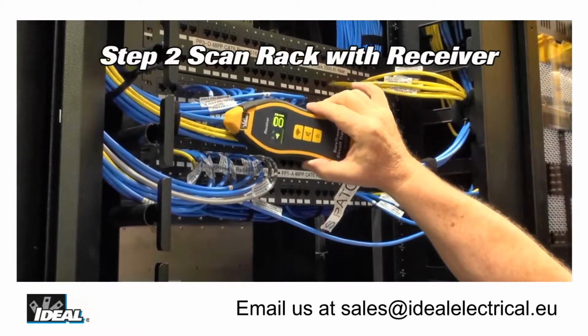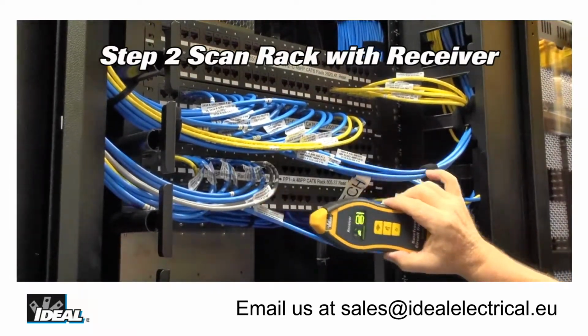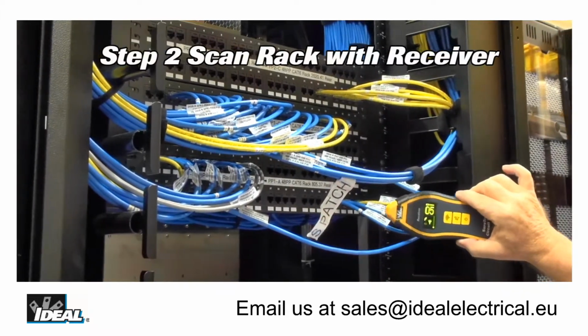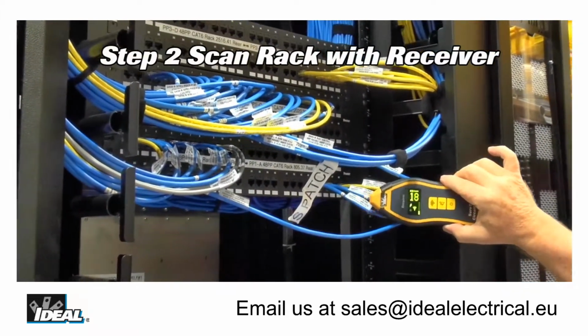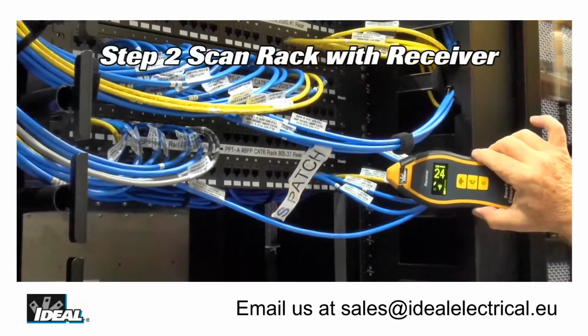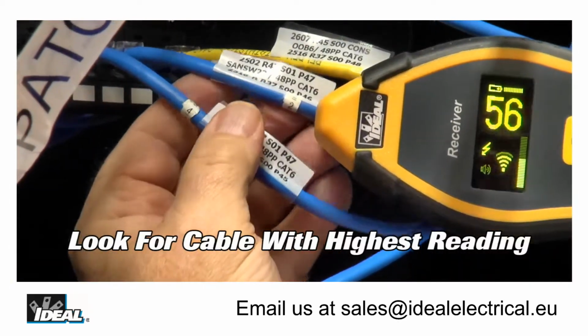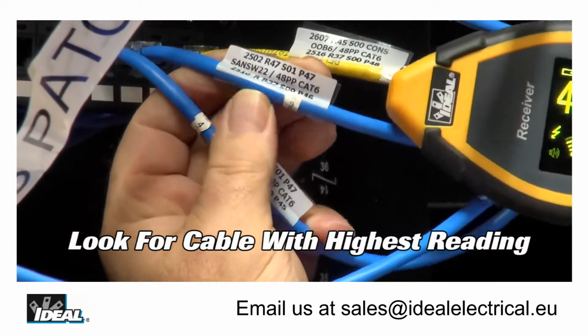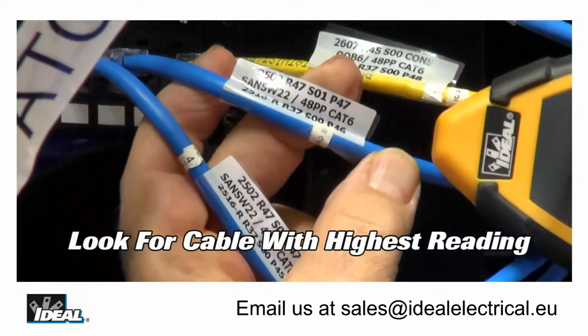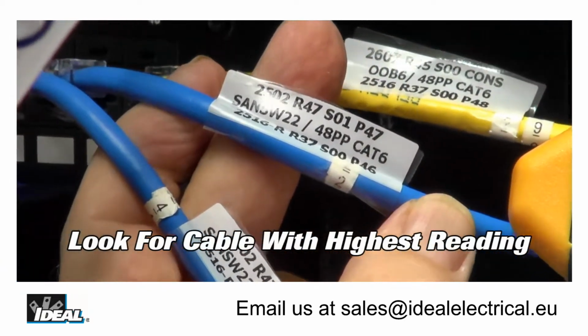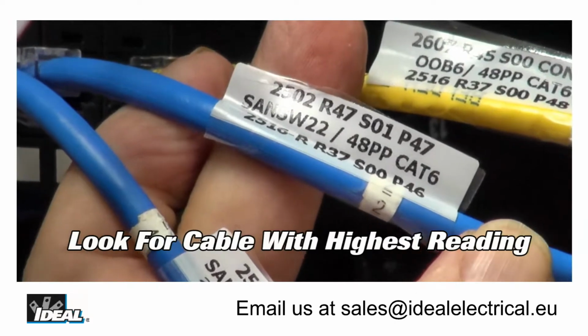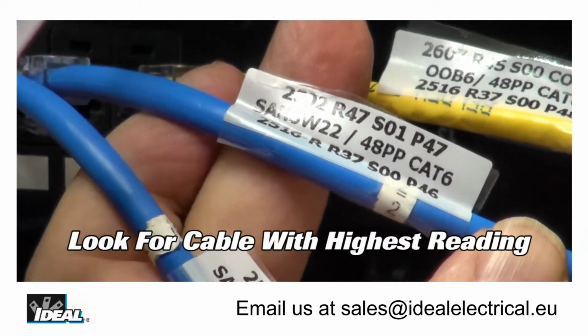Step 2 is to go to rack number 2516 and using the receiver, slowly scan all the cables in the rack using the highest sensitivity mode. Hold the receiver in line with the cable to get the strongest signal possible, and then reduce the sensitivity to properly locate the correct cable in the rack. As you can see, the receiver has quickly identified the cable being traced.